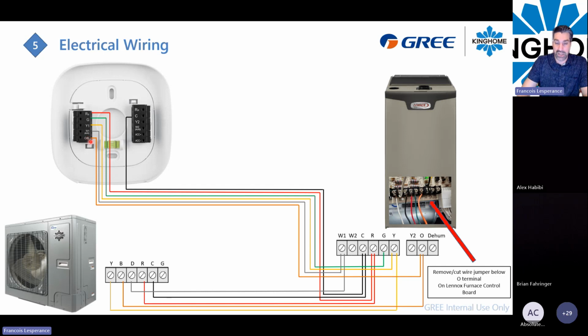You have a terminal called OB on the Ecobee system, and in the configuration of that thermostat, you need to configure it. This is for the reversing valve, so it needs to be configured active in heating. Because it's active in heating, we will use the wording B, okay? And so the B terminal will at a certain point be connected to the B terminal on the outdoor unit. But because some labels on the outdoor unit, coming from the furnace, are called the O terminal, O and B mean the same thing, but O is when it's active in cooling mode, and B is when it's active in heating mode. So you just need to know this slight difference between O and B.